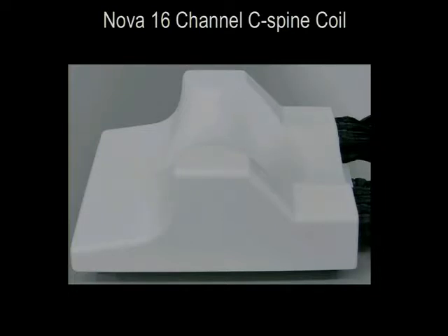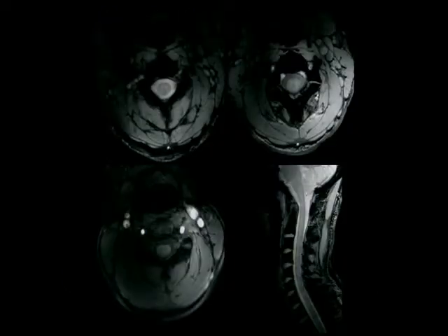Just to show you some recent results, I should give a disclaimer here that at Vanderbilt we use Philips scanners. This is a Nova coil that was just built not too far from here, actually, that was production. And we began to use this at 7T, really quite excited about them. Our anatomical images have some areas of, obviously, some B1 and B0 inhomogeneity. We're addressing that with dielectric bags and some other resources as well, looking at maybe smarter transmit pulses, et cetera.